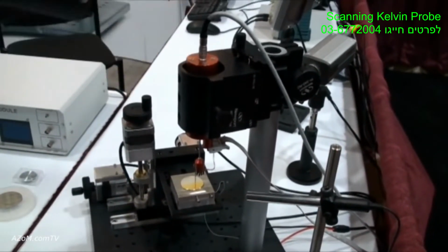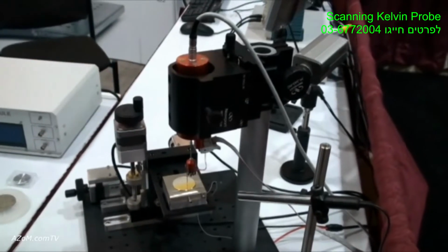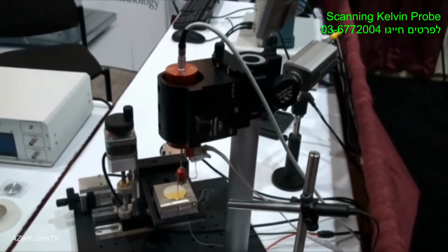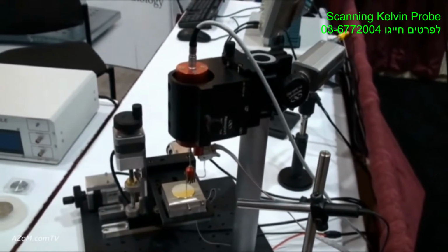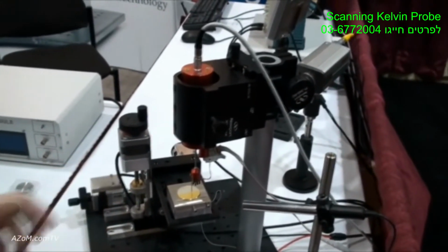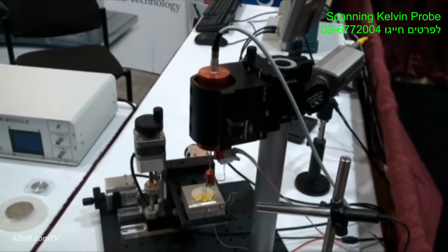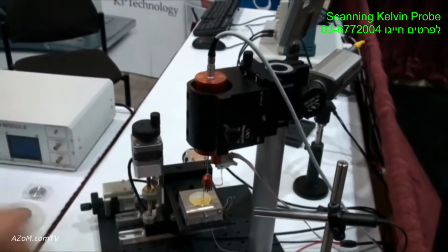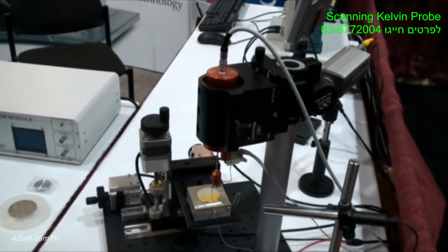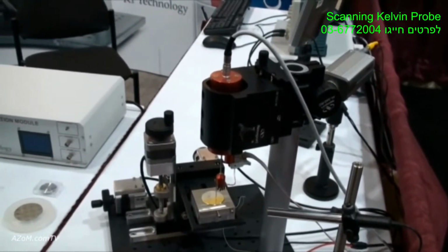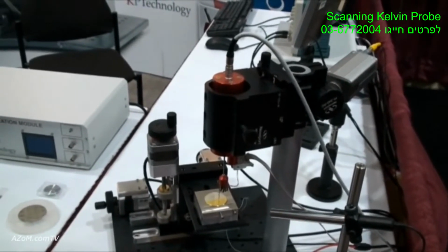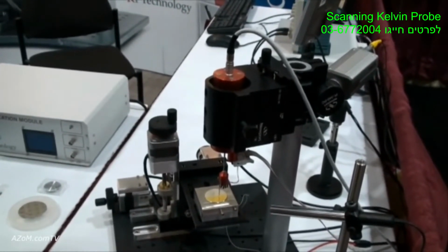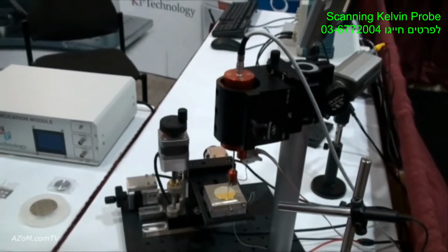So here we have a scanning platform with a tip that I can move up and down. The tip is vibrating and produces a signal at the oscillation frequency of the tip, which is about 70 or 80 hertz. The sample moves under the tip, and we form a three-dimensional map of the work function or surface potential of the sample. And because we have an interface here, we'll see that as a big work function contrast. It's an ideal technique in the sense it gives you real millivolt resolution. Other techniques give you a contrast, but you don't actually know what the scale is. So if I can move slowly around.